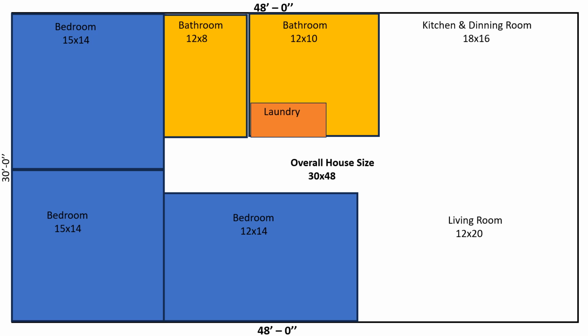But let's say in this situation, you've got a house where the living room and the kitchen, this open concept, has 10-foot ceilings, or maybe they're kind of gabled a little bit, architectural type ceilings. So we have a little bit more heat load because the ceiling's a little higher. So we're kind of deciding what to do. Let's just say, first thing we need to do is get our square footage, and we're going to get our square footage from each room.